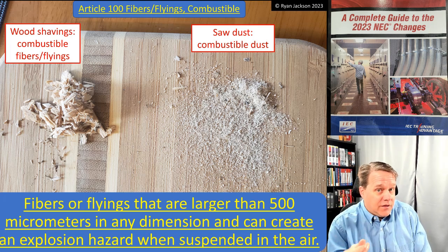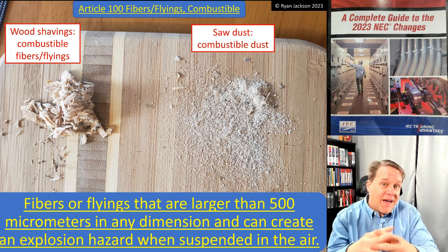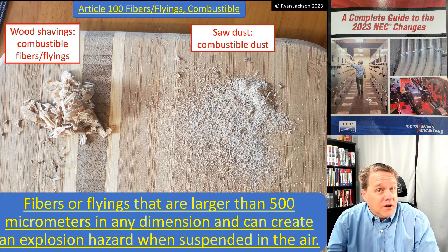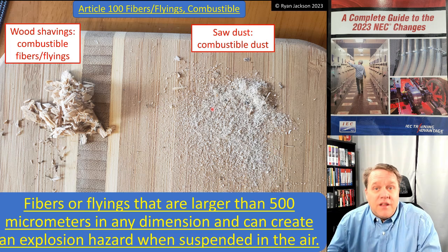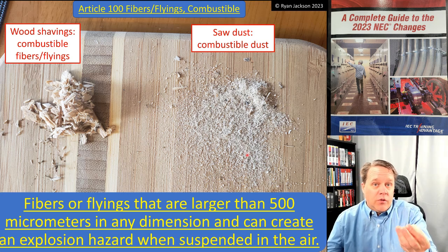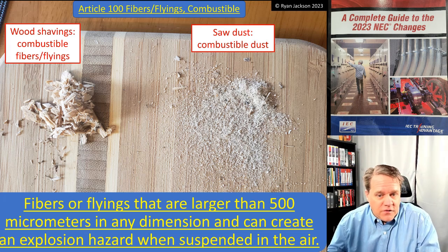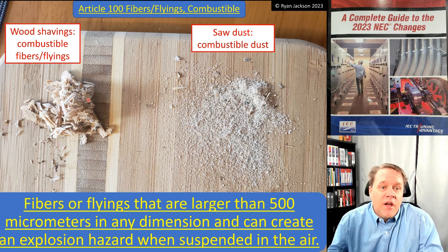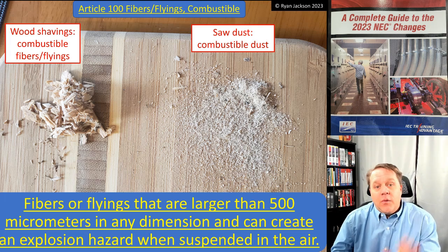If you can visualize the size of ground coffee, that is about 500 micrometers. If a material is finer than ground coffee and combustible, it is combustible dust. If it's larger than ground coffee and combustible, it's a fiber or flying. For example, sawdust on the right is combustible dust — finer than ground coffee — while wood shavings are combustible or ignitable fibers or flyings. That doesn't mean every wood shop needs Class 2 or Class 3 classification; whether there's enough to warrant area classification is discussed in Section 500.5.